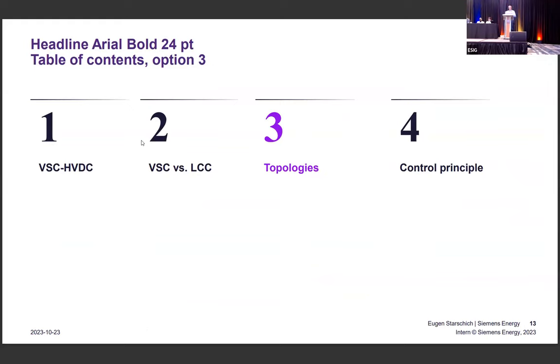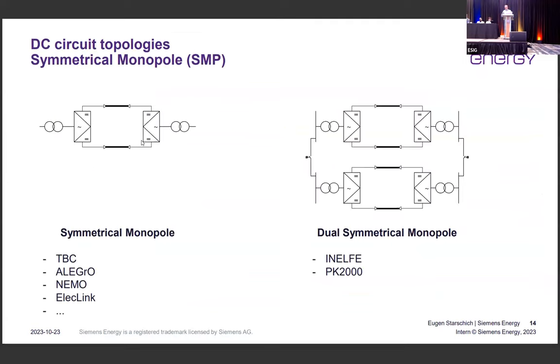Another point is now the configuration of the topologies, because this is a very crucial application: we have a VSC, but how do we make a system out of it? We are looking at different configurations. As mentioned before, to transmit the power over DC, we need just two conductors and two converters. This is the simplest topology we can get, called the symmetrical monopole. So, two converters, two conductors, and the power being transmitted in both directions, with all the flexibility. The symmetrical monopole is probably one of the most common configurations that you see right now in the market. We have the first transmission cable projects, Allegro, Nemo, ElecLink. There are many projects already built and in execution, which we have experience with.